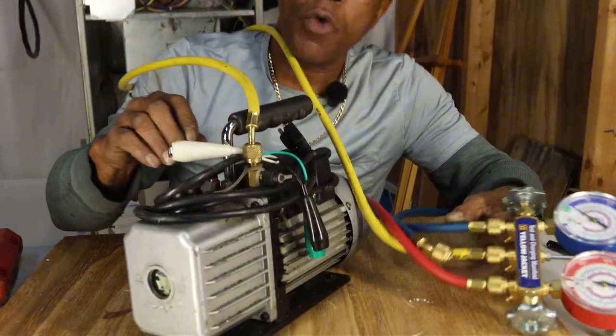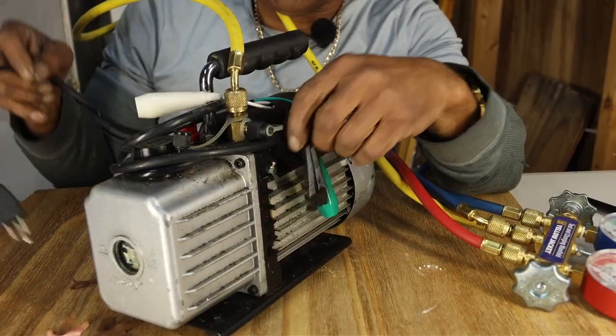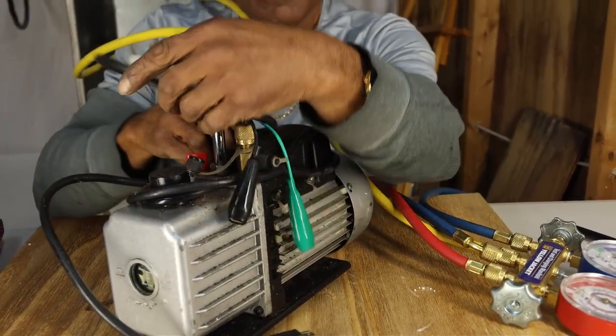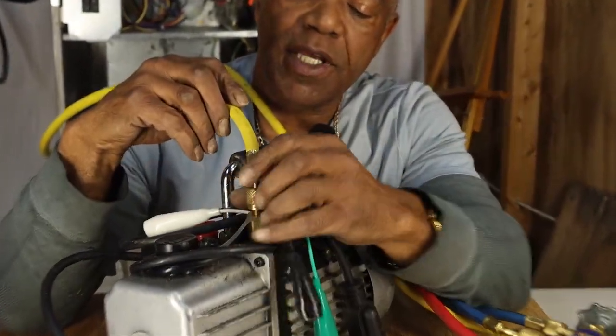But if you're going to work for yourself, you're going to need these tools down the road. Okay? Vacuum pump. And with the vacuum pump, what I have is this plug adapter. Okay? This allows me not to run an extension cord if there's no receptacle outside near the air conditioning unit. A lot of times, most people don't have a power receptacle near their air conditioning unit. And if the unit is in the backyard, if the unit's on the roof, I got to run an extension cord from the house all the way out.